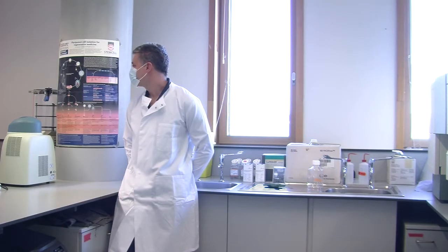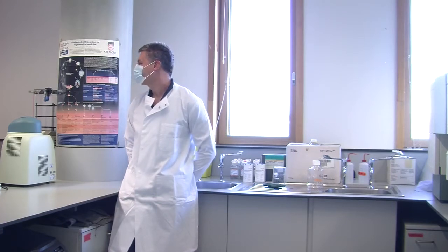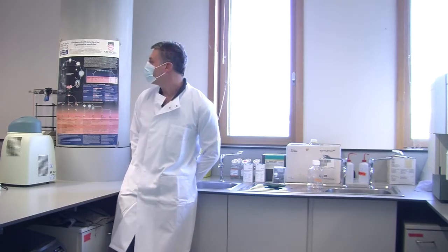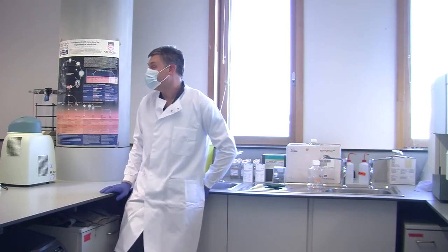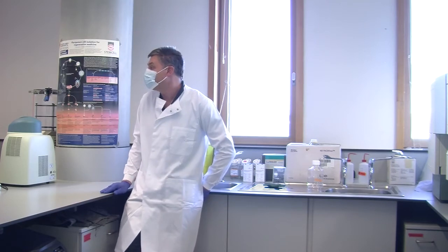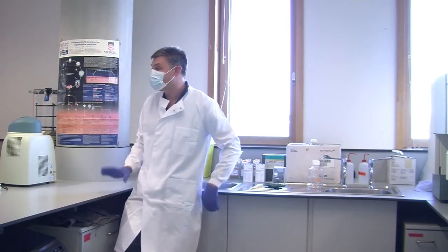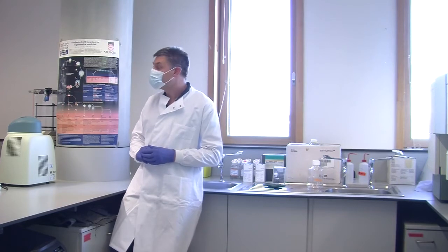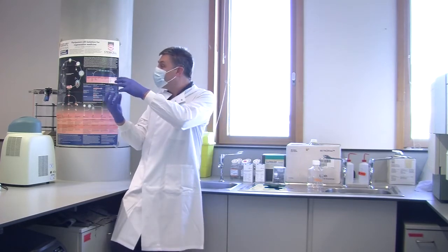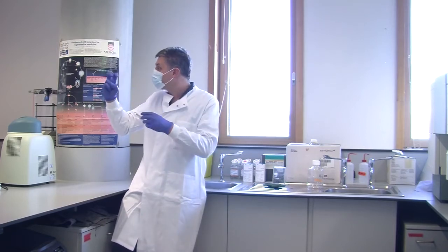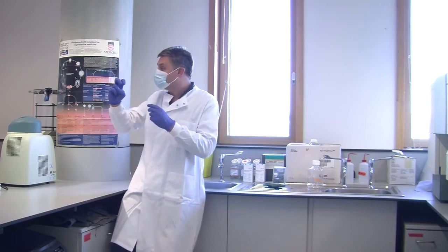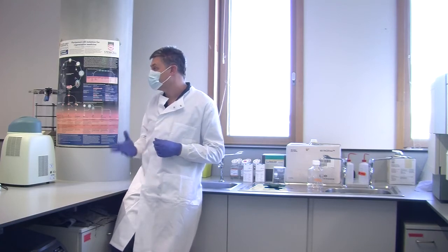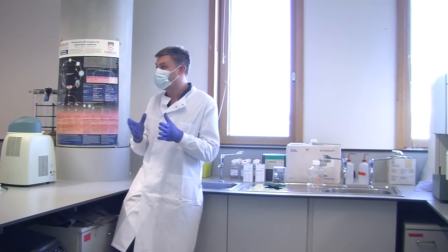What happens to this if you do not know about it? When I did my master's degree, because I did my master's and PhD down at Essex University, my master's supervisor was an advisor to one of the big centrifuge companies. And he showed me some pictures of a place he'd been called out to. And it was a spun-out centrifuge. So you have metal buckets that screw into a cap, and then you have hooks, and they hook onto little pins. So as the rotor spins, the bucket swings out on the hooks. And these are ultracentrifuges. These run sort of up to 1 million G. So they're ridiculously high speed.